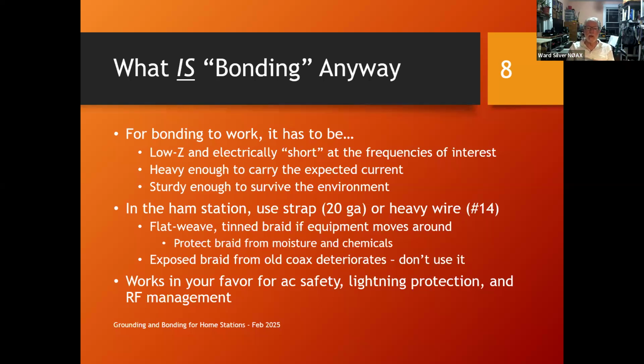The bonding also has to be heavy enough to carry the expected current. If you're bonding a tower to a ground rod and think it might get hit by lightning, we're talking kiloamps—that's a little scary to circuits guys like me. The conductor has to be heavy enough to carry that current and survive, not just vanish as an arc where everything blows up. That's why you see reliance on number 6, number 4, number 2, double-ought wires—they have to be heavy enough to carry the expected current.